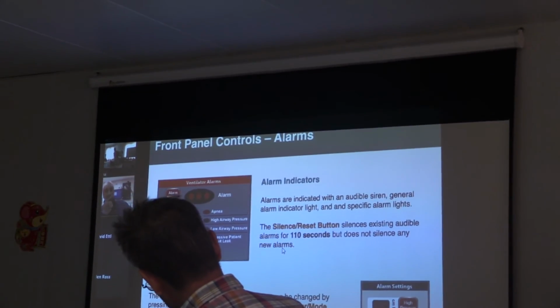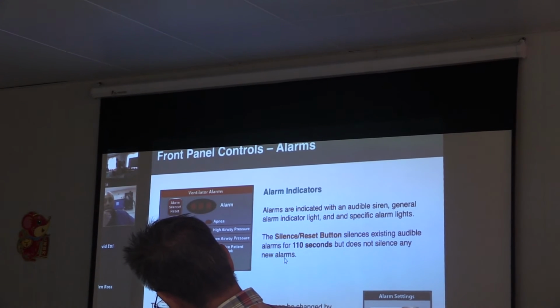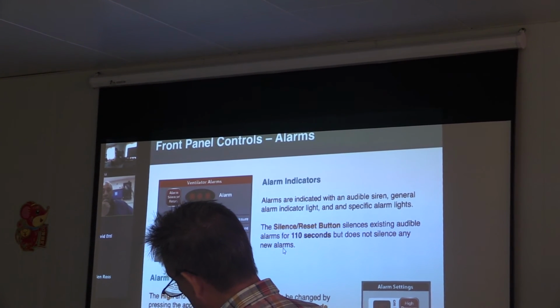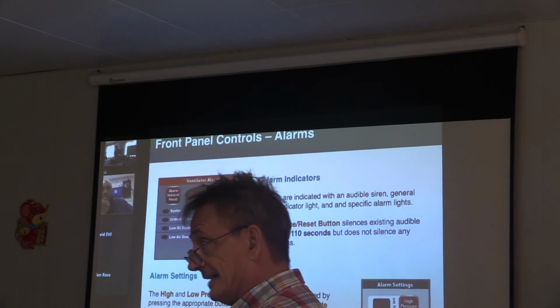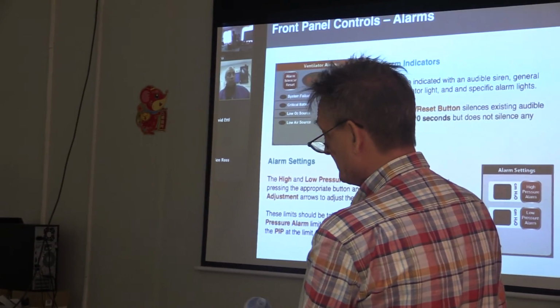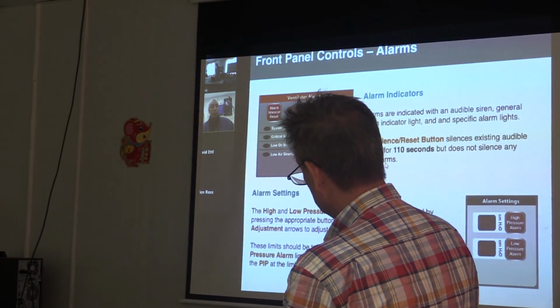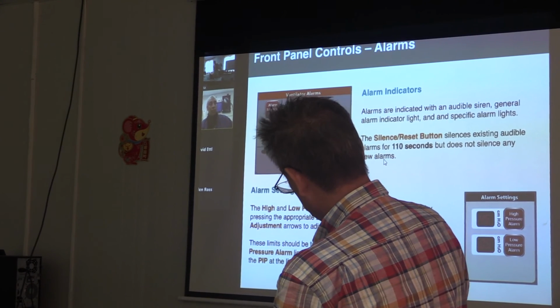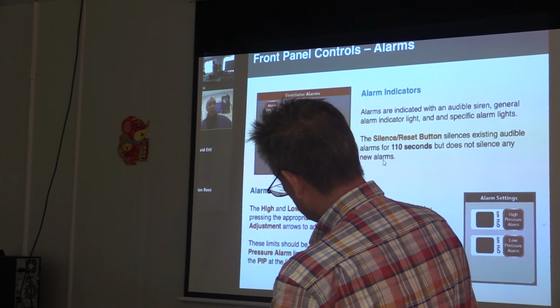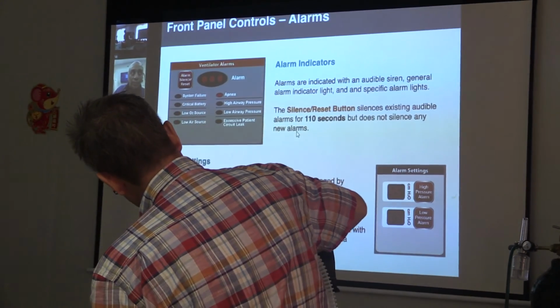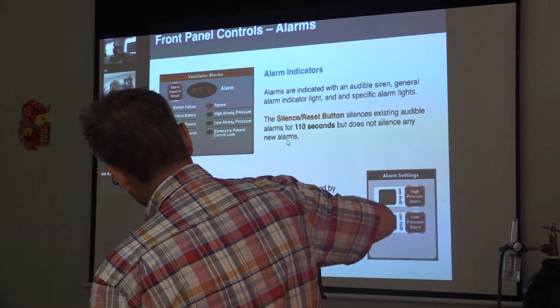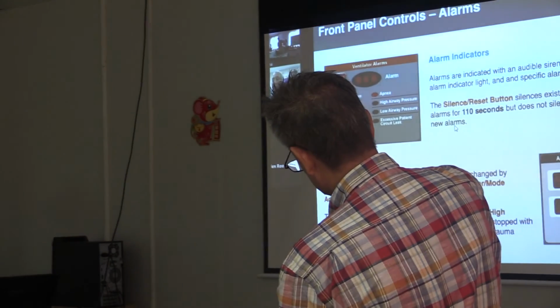John, Colin, any elaboration for that? Can I just show it on the machine? So we have set our alarms, the low pressure alarm at 5 centimeters of water, and there's no probe. Okay, this is the lock. We ventilated. Now we have a disconnection. See what's happening. It takes a little while to show. So already it doesn't go up. See, it gets under.